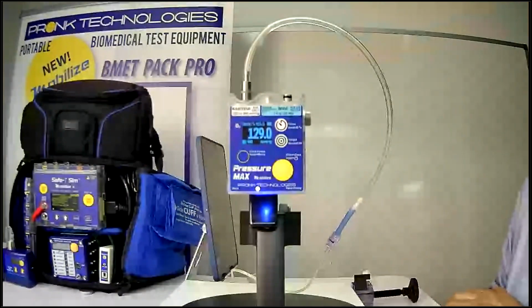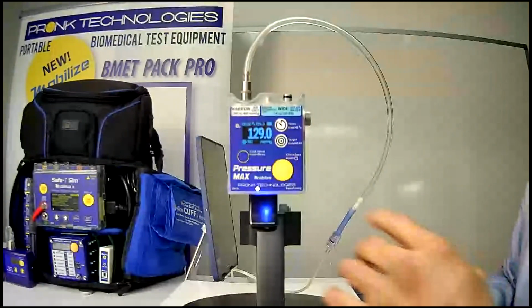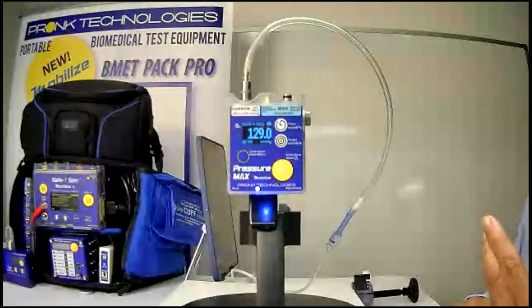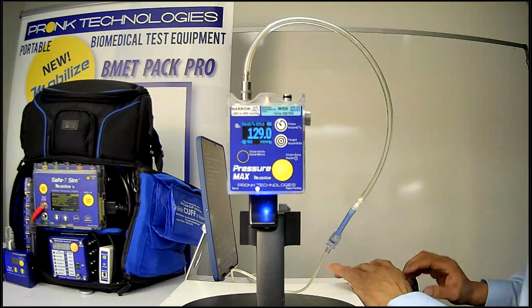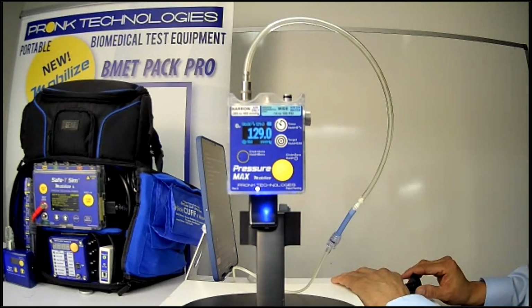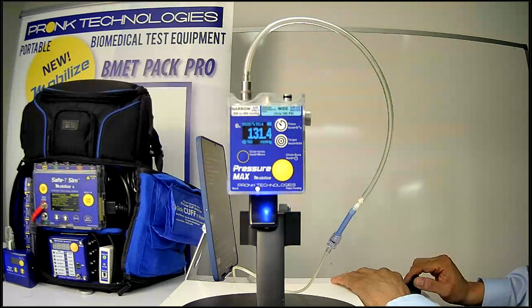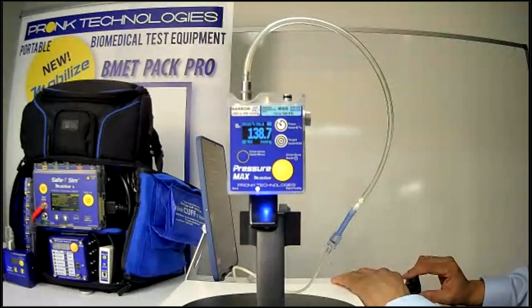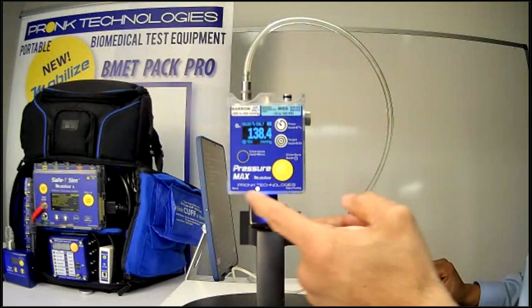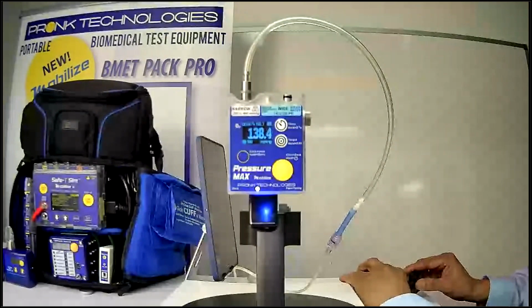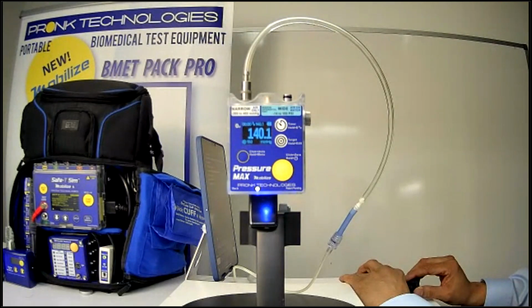That's my target for a particular target setting I had created, and it's in millimeters of mercury. So what that really allows me to do is, as I'm inflating the medical device and trying to confirm I've reached that target, the unit will illuminate blue while you're below the target pressure that you programmed. But once I get within the tolerance that I programmed, and in my case, I programmed it so that it needed to be within 1 millimeter of mercury, when I get to that pressure target, the unit will turn green.